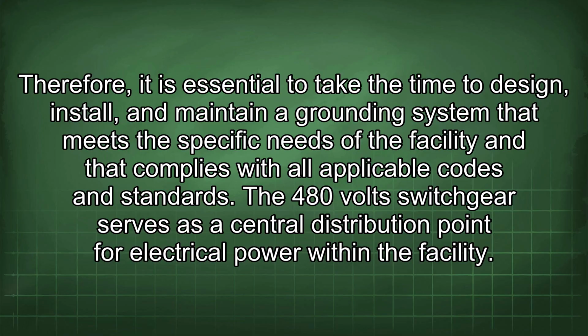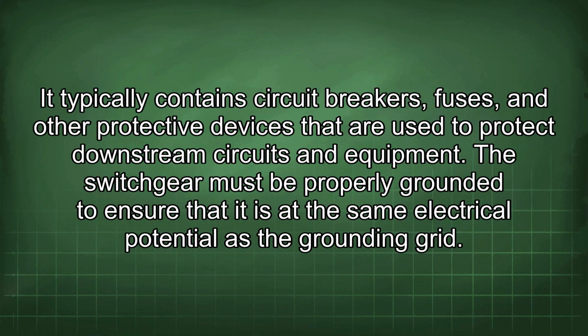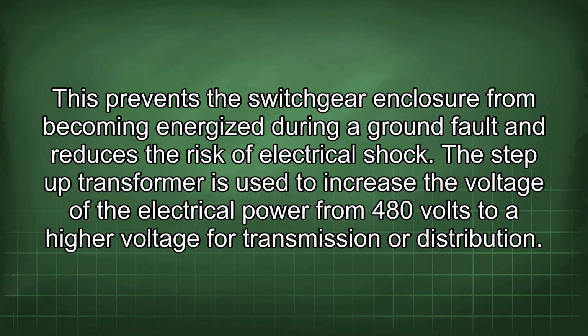A 480-volt switchgear serves as a central distribution point for electrical power within the facility. It typically contains circuit breakers, fuses, and other protective devices that are used to protect downstream circuits and equipment. The switchgear must be properly grounded to ensure that it is at the same electrical potential as the grounding grid. This prevents the switchgear enclosure from becoming energized during a ground fault and reduces the risk of electrical shock.